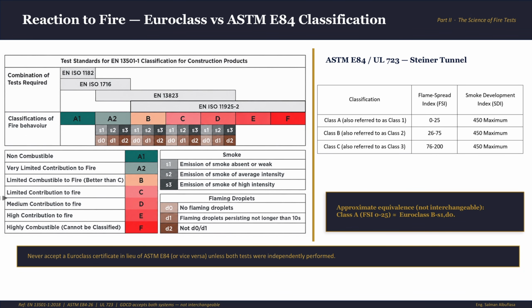So, in conclusion, EN 13501 gives you the full picture, multiple tests, multiple scenarios, a detailed classification from A1 all the way to F. ASTM E84 is more direct: one test, two numbers, three classes. And this is exactly where codes and standards come in, especially local codes, which are tailored to meet the local realities. They specify which class is required for every occupancy type and every location within it. Each one has a defined minimum class for exits, for corridors, for floors, and other spaces.